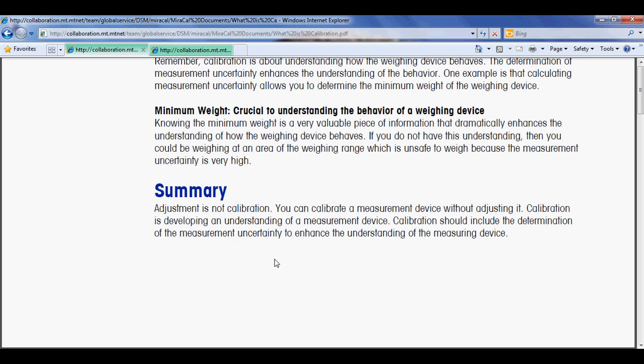So in summary, adjustment is not calibration. You can calibrate a measurement device without adjusting it. Calibration is developing an understanding of a measuring device, and calibration should include the determination of the measurement uncertainty to enhance the understanding of that measuring device.